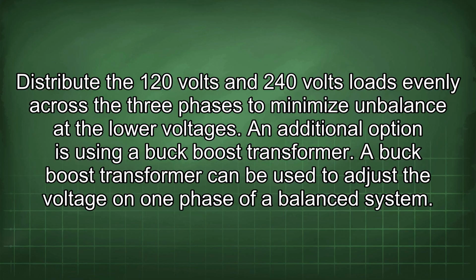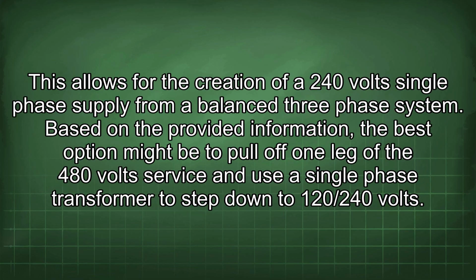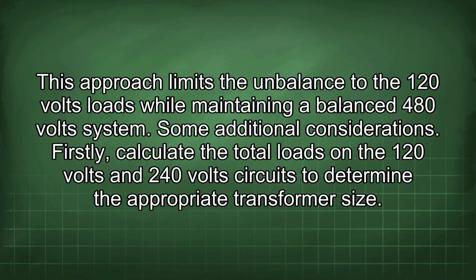A buck-boost transformer can be used to adjust the voltage on one phase of a balanced system. This allows for the creation of the 240 volt single-phase supply from a balanced three-phase system. Based on the provided information, the best option might be to pull off one leg of the 480 volt service and use a single-phase transformer to step down to 120/240 volts. This approach limits the imbalance to the 120 volt loads while maintaining a balanced 480 volt system.